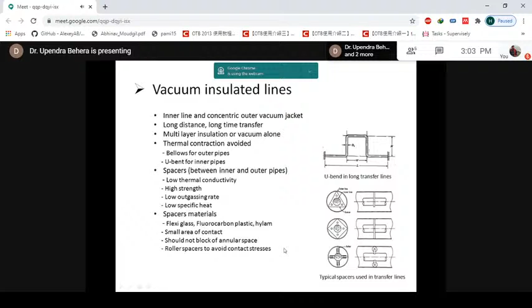Sometimes roller spacers are also used to avoid contact stresses between these two lines. And one effective joint for long transfer lines, or if you want to dismantle very frequently, is this bayonet joint, which is a high performance cryogenic joint, as I have explained earlier. From the first line it goes to the end where the vacuum extent is there, and it fits to the other line where the gap between the two is minimized, so that the male portion telescopes within the female portion with a clearance such that no liquid can flow between these two spaces, and gaseous convection is suppressed.